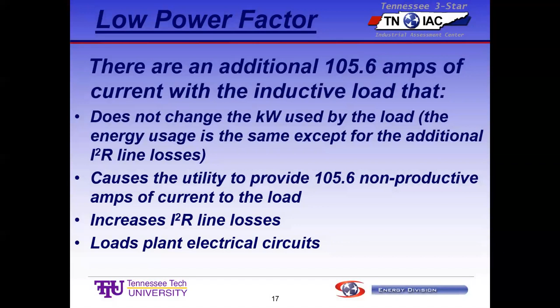Okay, so this additional 105.6 amps of current that occurs because of the inductive load doesn't change the kW reading on the meter, except that the additional amps will have some I²R loss. I can't put another 105.6 amps through a wire and not have some additional losses. So that's a small loss. That's usually 1% or 2%. That's not huge, but it's there. It causes the utility to provide this extra current.